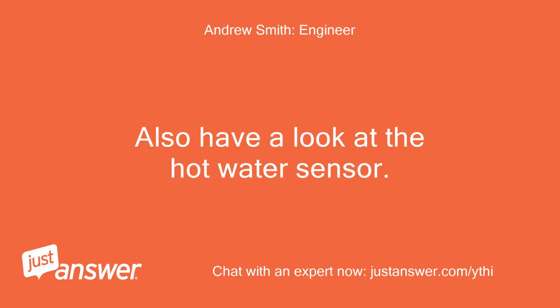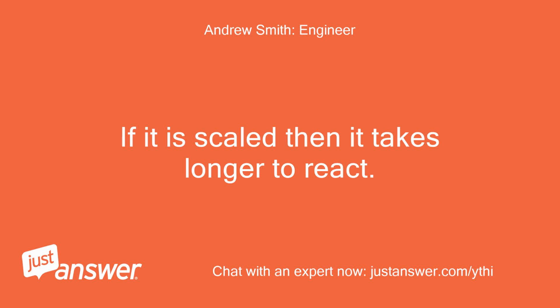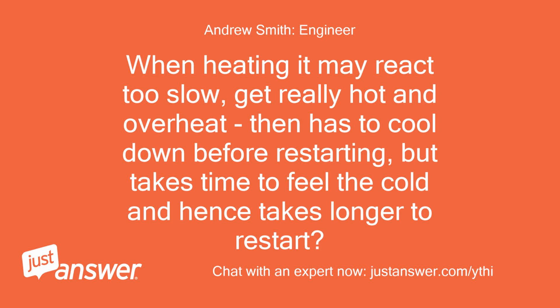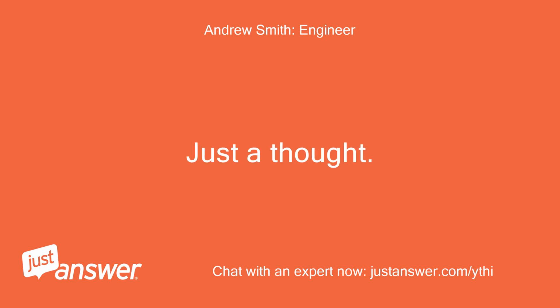Also have a look at the hot water sensor. If it is scaled, then it takes longer to react. When heating it may react too slow, get really hot and overheat, then has to cool down before restarting, but takes time to feel the cold and hence takes longer to restart? Just a thought.